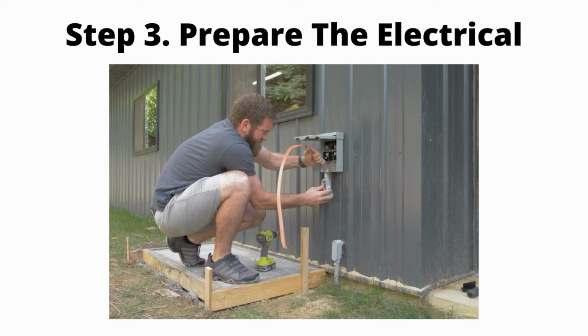If you have a 115-volt unit, you will need to get the electrical from an outlet. You will need to run the wires inside a water-tight enclosure. We typically use a liquid-tight connection into a disconnect box. From the disconnect box, you will need to run the electrical to the outdoor condenser.